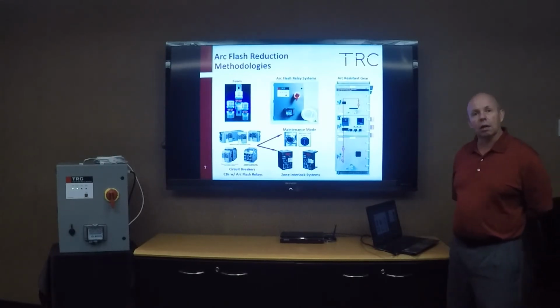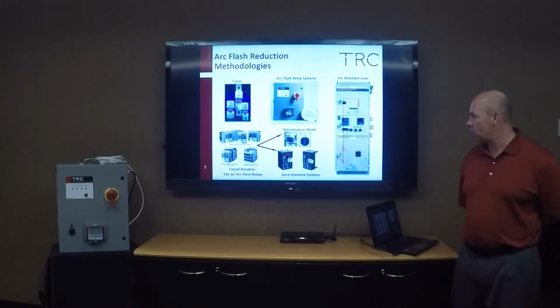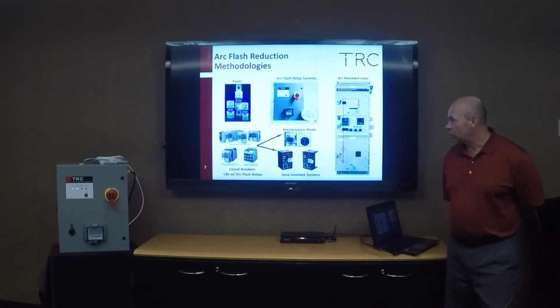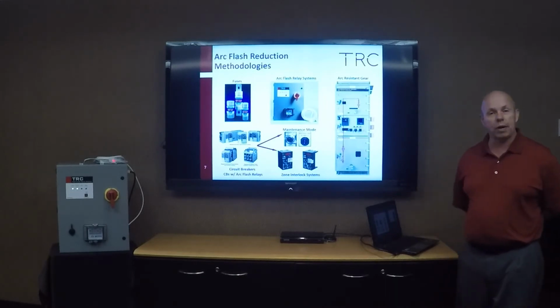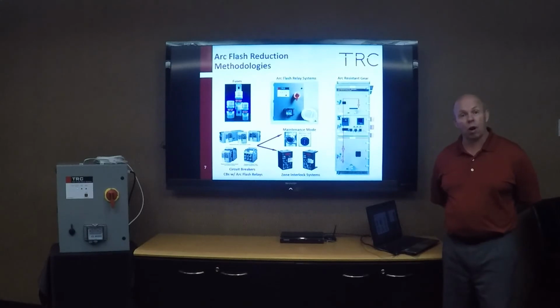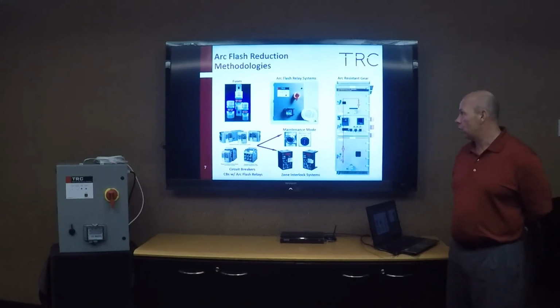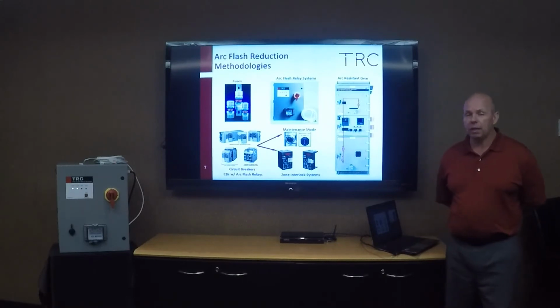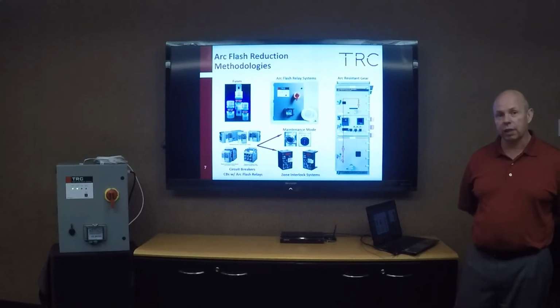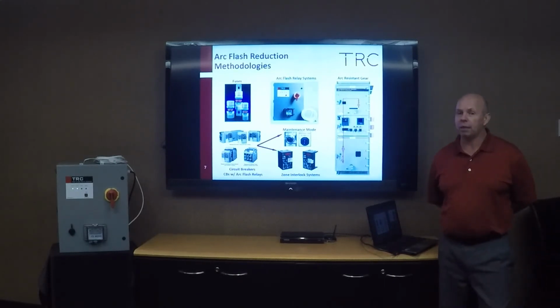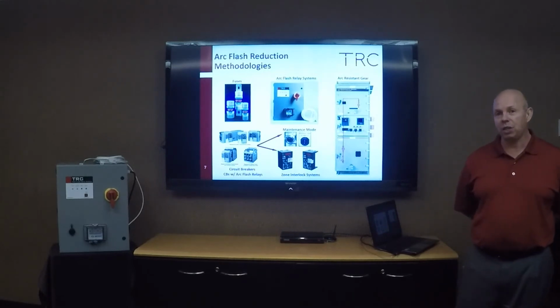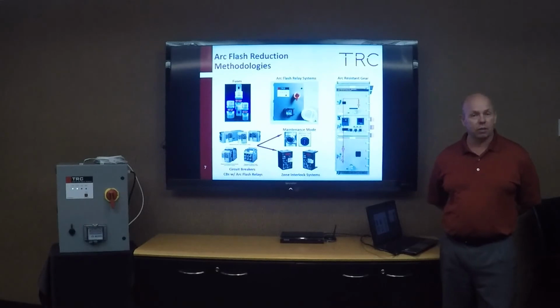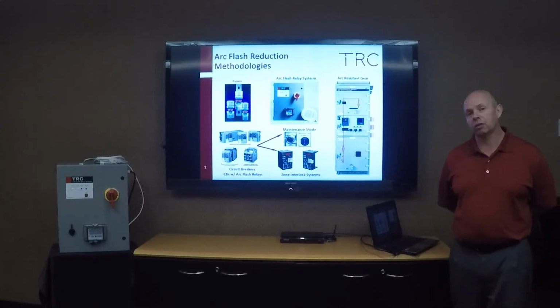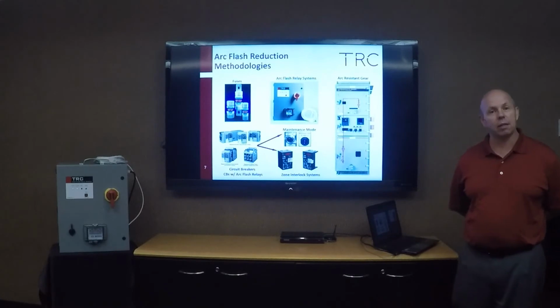Other types of methods that are approved are circuit breakers with maintenance mode or zone interlocking systems. Switchboards that contain molded case circuit breakers, you can get zone interlocking, which actually allows for coordination and fast tripping times for arcing events as well as short circuit current events. The maintenance mode circuit breaker has been around for a number of years now. The maintenance mode circuit breaker can be a good option for reducing incident energy, but you've got to remember that the arc flash mitigation is not something that's done automatically. The reason is that the maintenance mode circuit breaker requires personnel that are going to be working on or near the energized circuit to actually energize or de-energize the maintenance mode circuitry.